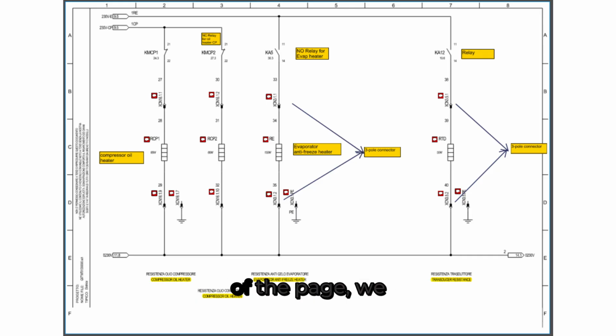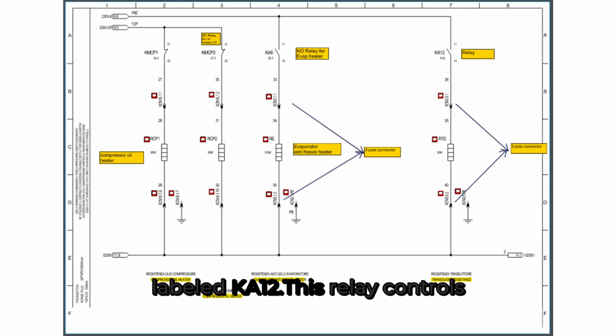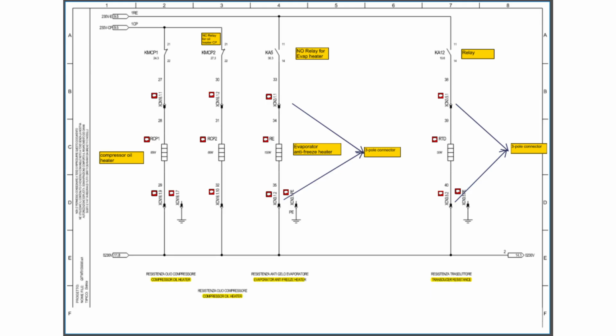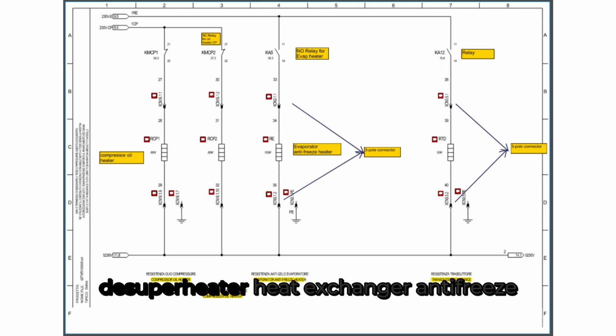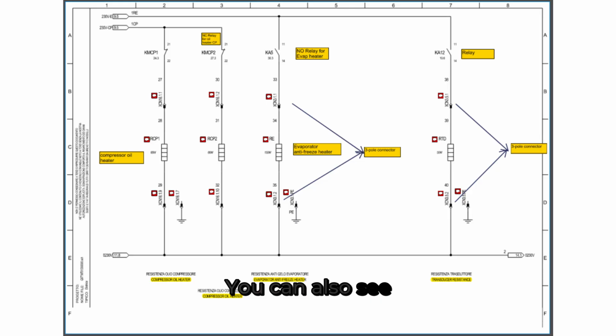On the right side of the page, we have another relay coil labeled KA12. This relay controls a resistive element labeled RTD, which stands for desuperheater heat exchanger antifreeze heater. You can also see 3-pole connectors on both sides of the RTD, one for incoming power and one for the return, making it easy to service or replace these components in the field.